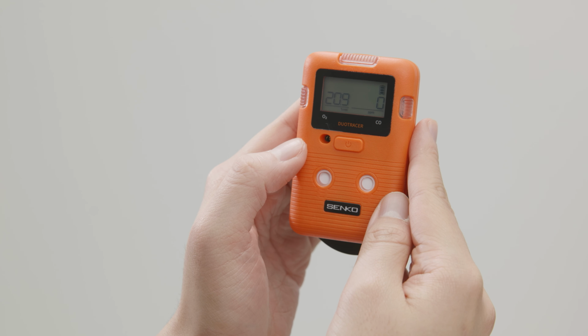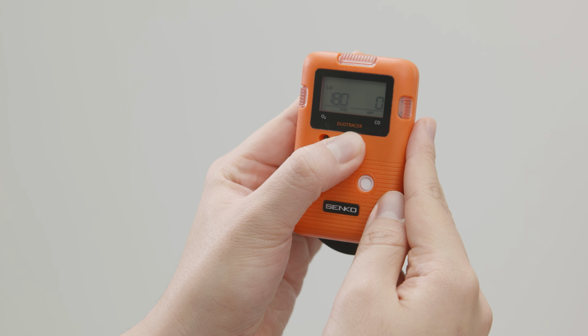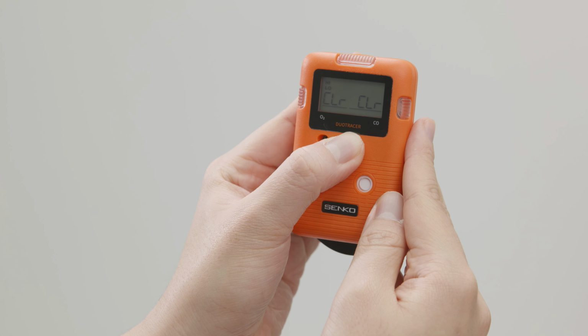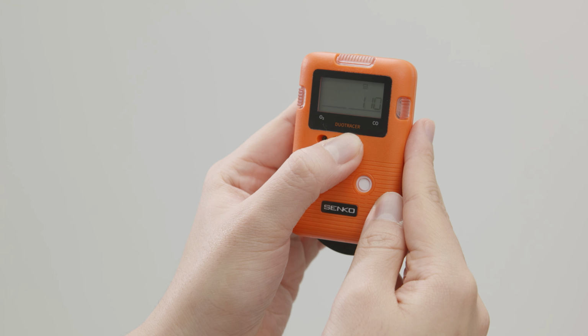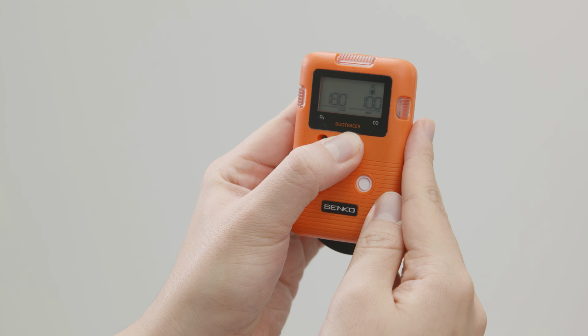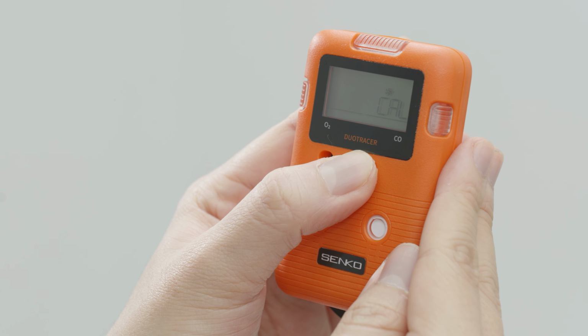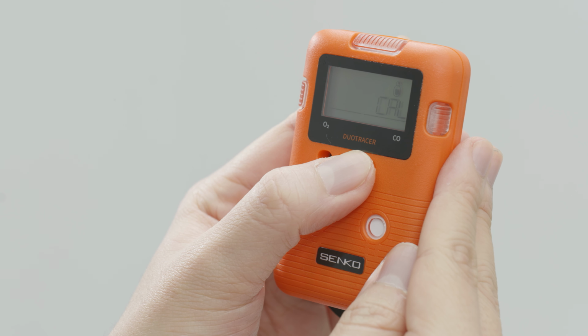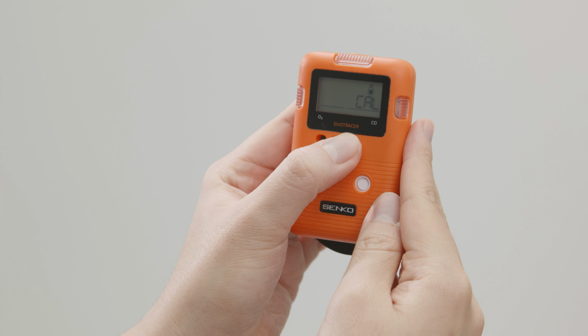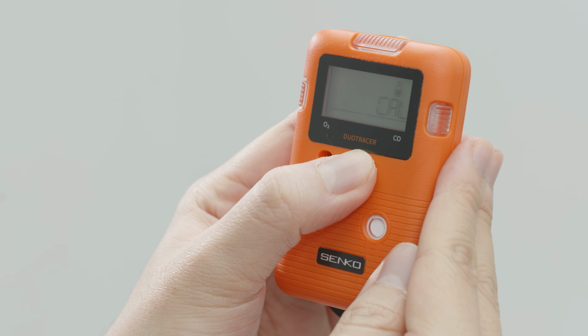Now, let's walk through the zero and span calibration process of Duo Tracer. It might seem a bit complicated at first, but once you understand the icons shown on the LCD screen, anyone can perform calibration easily. When you see the cylinder icon on the display, that means calibration. With that cylinder icon on the screen, press and hold the button for about 2 seconds and you'll see the following menus appear one by one: zero calibration, span calibration, bump test.